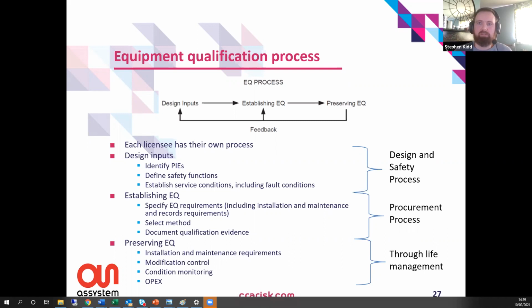And then there's preserving EQ. So we need to manage it through the life of the plant. The installation and maintenance requirements: we need to make sure that every time we maintain the equipment, we aren't undermining any of the qualifications. So electrical cabinets, for example, we may be making claims on them being sealed against water ingress. We need to make sure that when we undertake maintenance, we reinstate that capability at the end so that we haven't undermined the safety case.